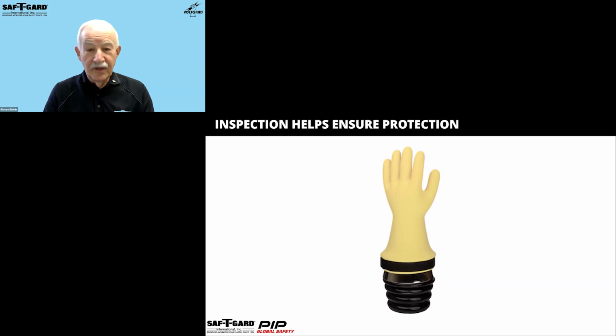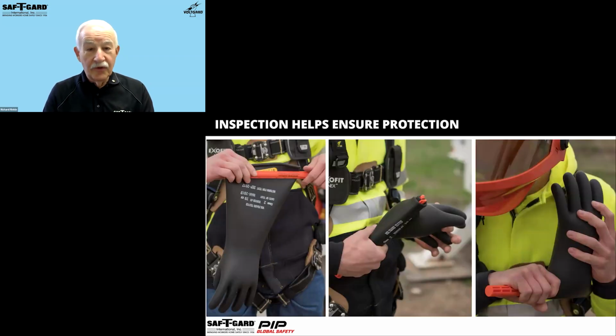And then you get to see if there's any damage to the glove that might not be otherwise visible unless viewed after inflating. If that portable inflator is not available, use a rubber glove inspection tool or roll the rubber insulating glove to lightly trap the air inside. So I can show you how this all works. We can take this rubber insulating glove and we put the clothespin type on it. And by rolling it up, it's trapping the air inside so you can see if there's any physical damage to the glove. In addition, if there's been any electrical damage, an electrical failure, by rolling it up, you can see much closer where it's circled that there is a pinhole there, which is from the electrical failure. So this is a real neat tool when that other pump inflator is not available. So let's go back and take a look at some of this again.